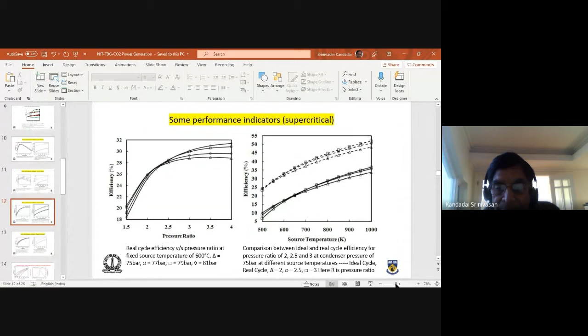This is for various pressures. Actually, there's not much difference—they bunch together. So for efficiency versus pressure ratio, the optimum comes only for 75 bar. As you keep increasing further, the optimum pressure ratio shifts, because as the pressure ratio increases, your efficiency also keeps increasing.